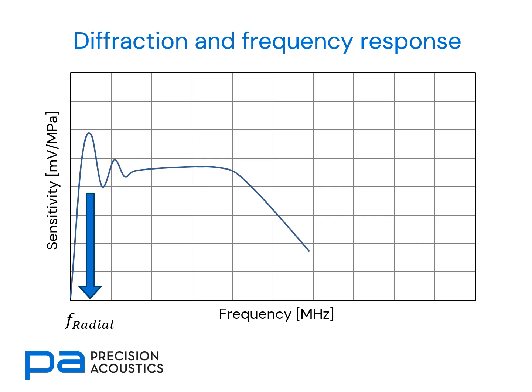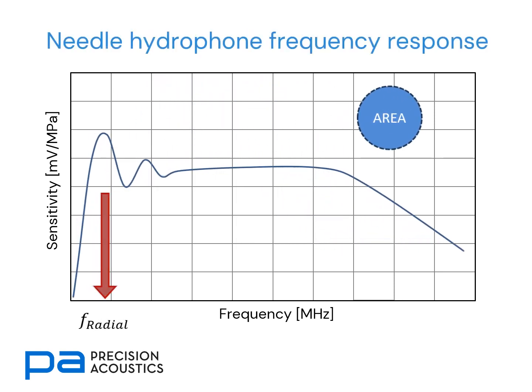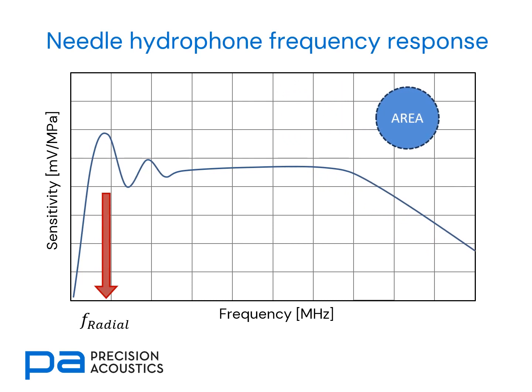Notice here where the peak of the radial resonance is for a larger area needle hydrophone. If we move to a smaller area needle hydrophone, the shape remains the same, but expands along the frequency axis, and we also notice that the peak in the response has moved upwards.